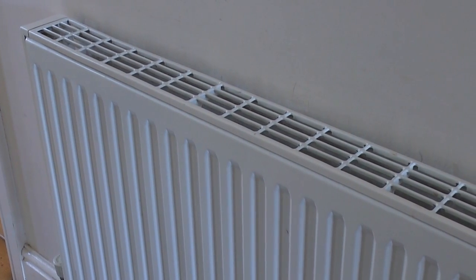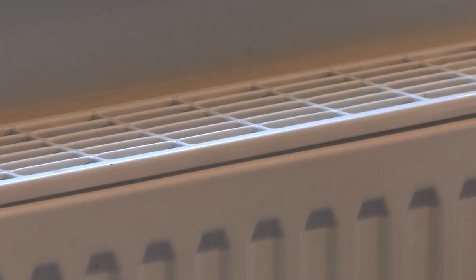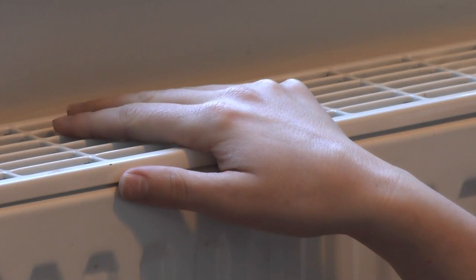If any of the radiators are cool while others are warm, this could be a sign that you need to do some maintenance. If any of the radiators are cool at the top, then this might mean there's air trapped inside and the radiator needs bleeding. You can easily do this yourself, but if you've not done it before, it'd be best to contact a heating engineer to help you.